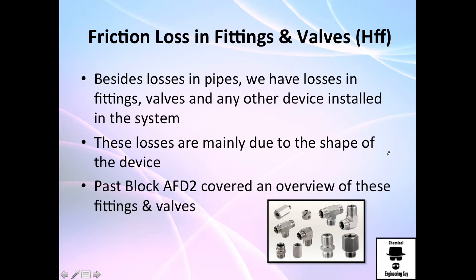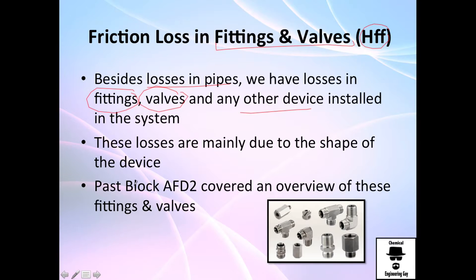Let's talk about fittings and valves and the friction loss due to these two things. We're going to use HFF instead of HFS. Besides losses in pipes, we also have losses in fittings, valves, and other devices installed in the piping system. This is mainly due to shape — for example, a pipe that changes to a smaller diameter, or a splitting, where the fluid hits a geometry change and you lose energy.